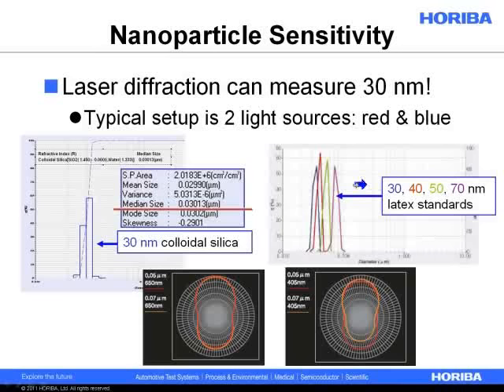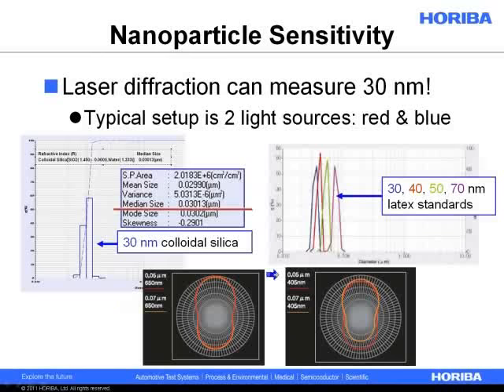There are different solutions on the market — some people use three lasers, some use different ways of polarizing the light. A very typical setup, certainly in Horiba and some other vendors, is to use a red laser and some sort of blue light source. In the Horiba LA-950, we use a blue LED. The effect is basically sensitivity and resolution for very small particles. If all you use is a red laser diode at 650 nanometers, you can't really distinguish the scattering pattern between 50 and 70 nanometers. But if you investigate with a blue light source at 405 nanometers, you can begin to see differences.